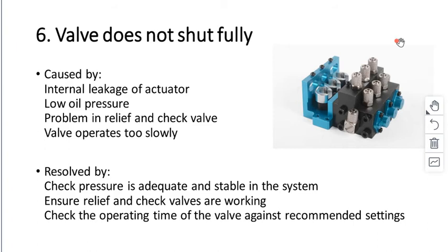So you check pressure is adequate and stable in the system. And this is an argument that if you build or design a system yourself, you try to have pressure gauges all over the system to get a good idea of what's going on in the hydraulic system. Ensure relief and check valves are working, and check the operating time of the valve against recommended settings.